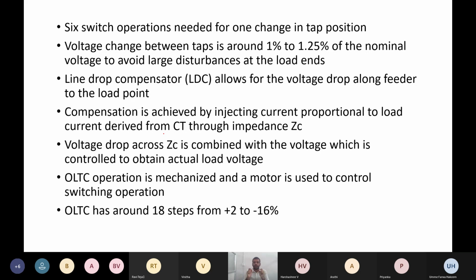So that's why we are using line drop compensators, called LDC. This allows for the voltage drops along the feeder to the load point. It is necessary to use LDC for tighter regulation of the transmission voltages. If you go for transmission line voltages, at that time we have to use line drop compensators. These allow for the voltage drops from the feeder to the load point, so that the OLTC, the on-load tap changer, will work at the actual loads.